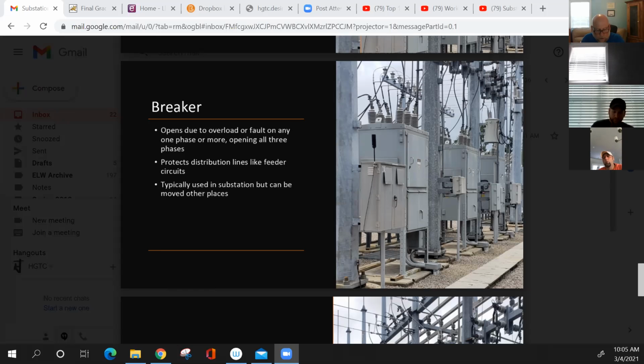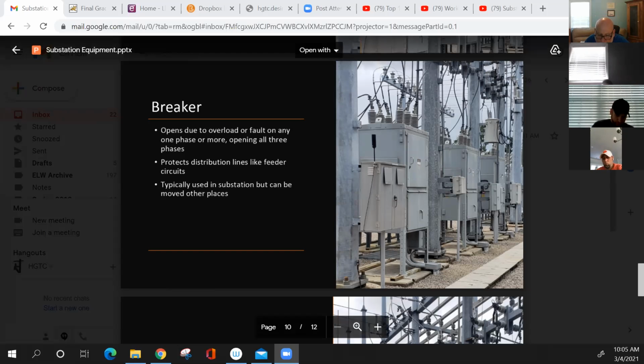I'd say all three. All three, that's right. You just don't want one phase to be out because you're going to have an imbalance out in the field. Three-phase customers may at that point start single phasing, and that's bad for them. So it's designed, if you get a fault on one phase or two phases, then all three phases are going to open up. And you can see where it leaves the bottom of the bus side disconnect and goes into the top, the bus side of this breaker.